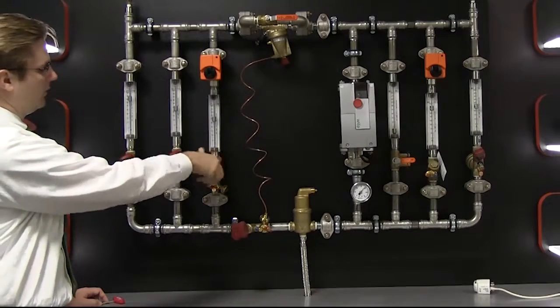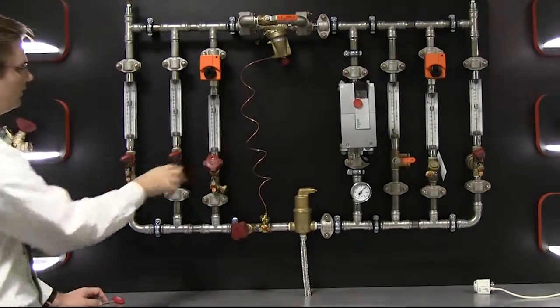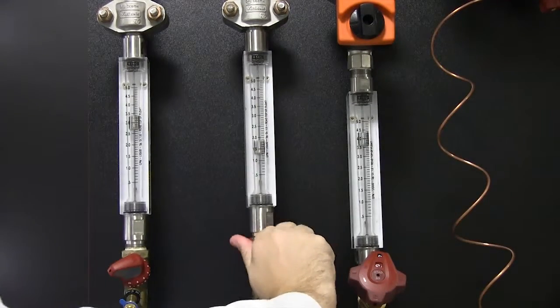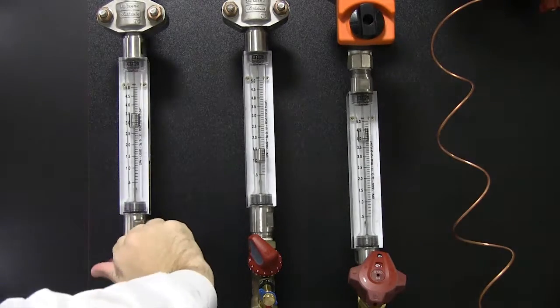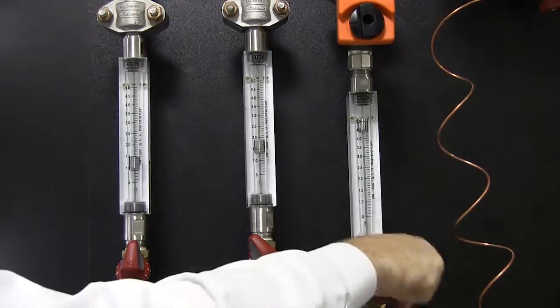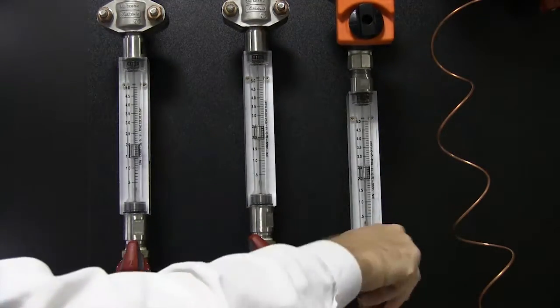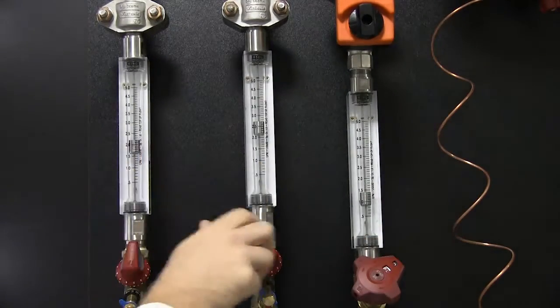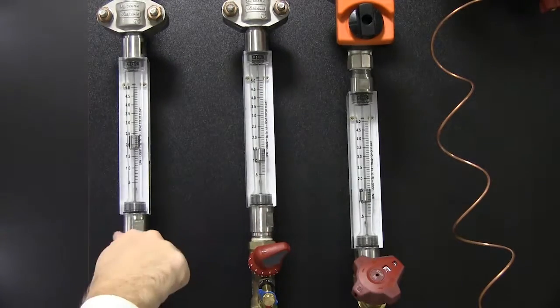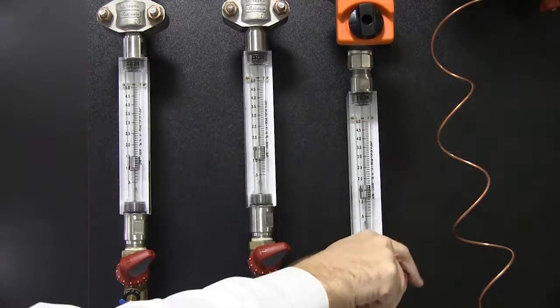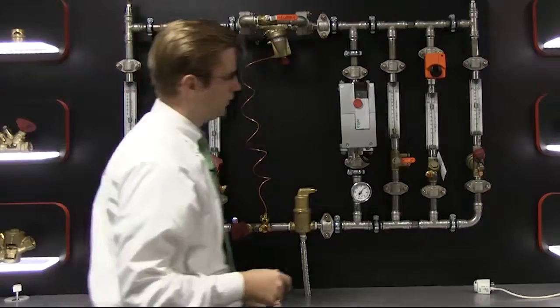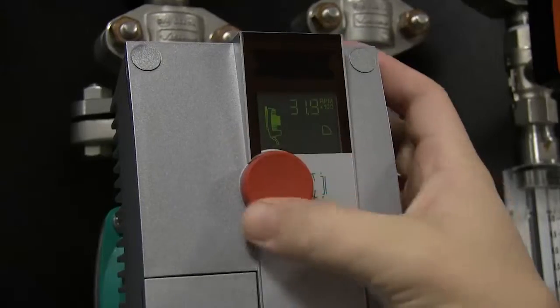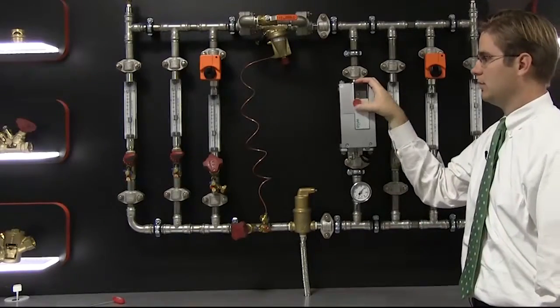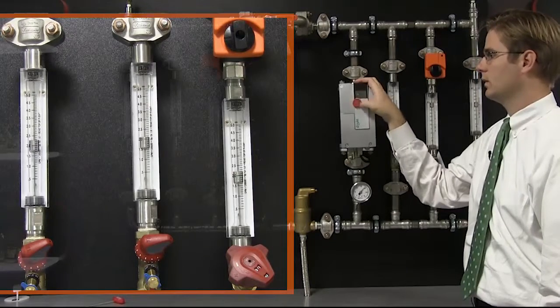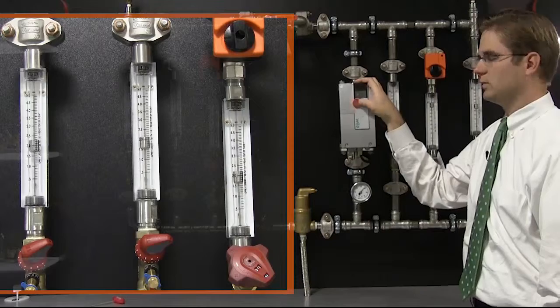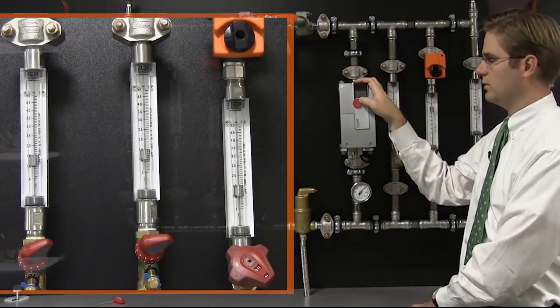When you go to balance a building with manual balancing valves, you can start at one point, set it to, let's say, 1.5 GPM. Go to your second point, set that to 1.5 GPM, and go to your third point and set that to 1.5 GPM. What you'll notice, though, with manual balancing valves is that as I adjusted one valve, the others changed. So now I have to go and readjust the other 2 valves to get them to their proper flow rate. Also, when I have a pressure increase, when part of the building shuts down, I get an increase in flow rate at the manual balancing valves. And when there's a pressure decrease, I get a lower GPM.